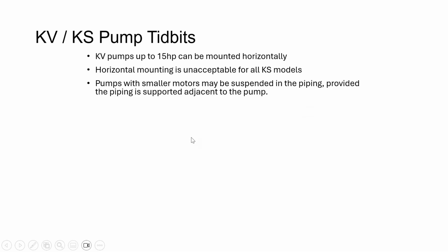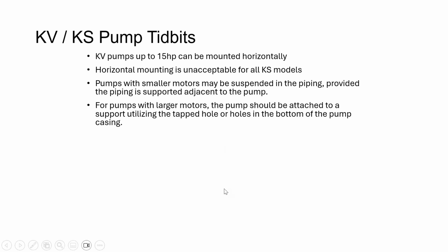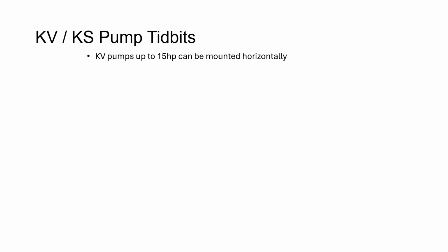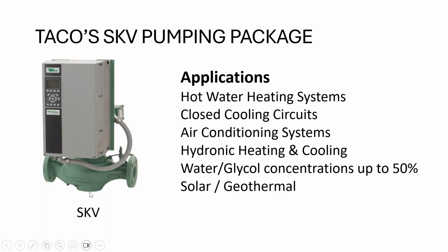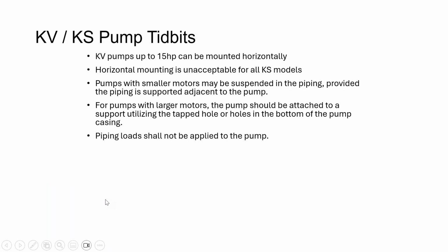Pumps with smaller motors, I think it's 15 and less, maybe 10 and less, may be suspended in the piping. I'm going to show you some piping arrangements in a few seconds here. This is provided the piping is supported adjacent to the pump. So something to think about or consider there as well. Larger motors, the pump should be attached to a support utilizing the tap holes. So down here at the bottom, there's 4 tapped holes on the casing, right? So you can actually mount the support there, and that's actually an item you can purchase from Taco. It's just a little stand, so you can mount that there as well.